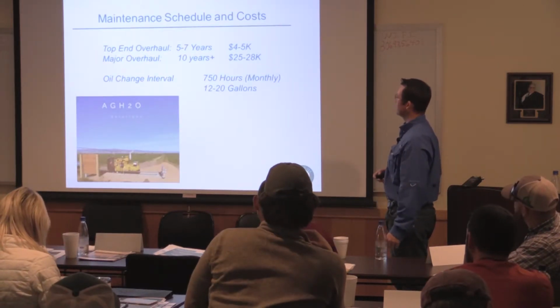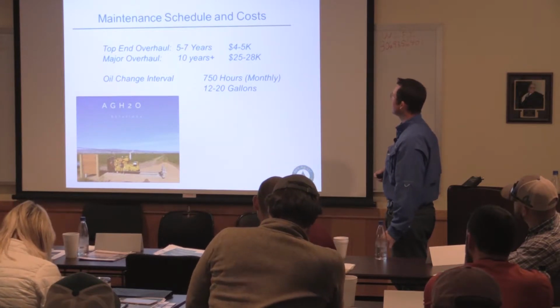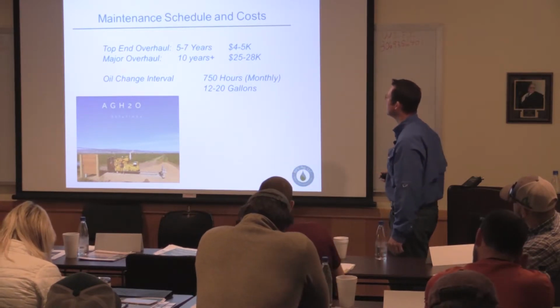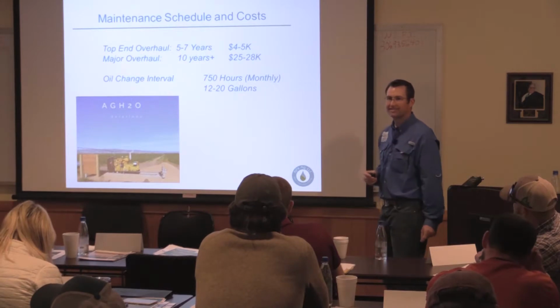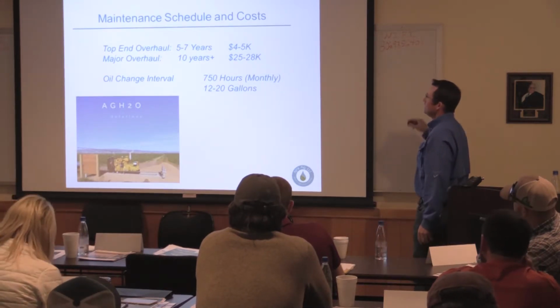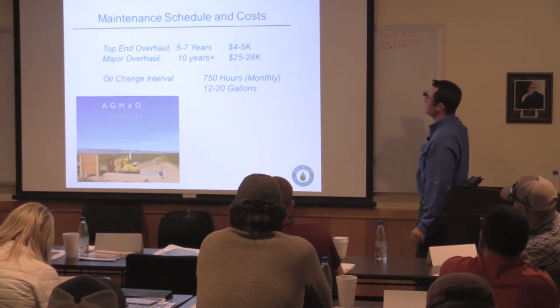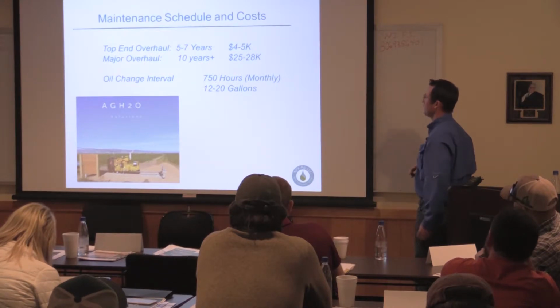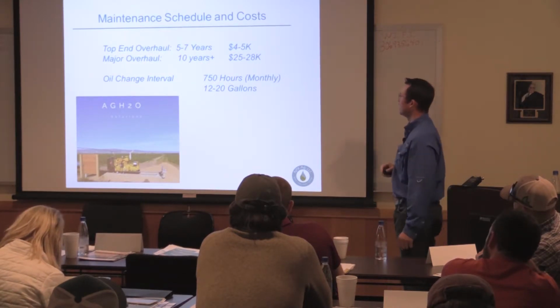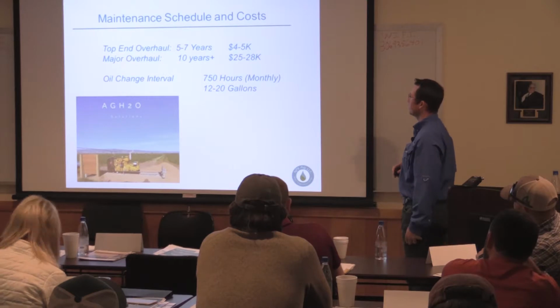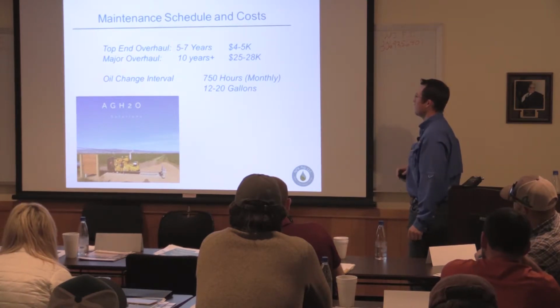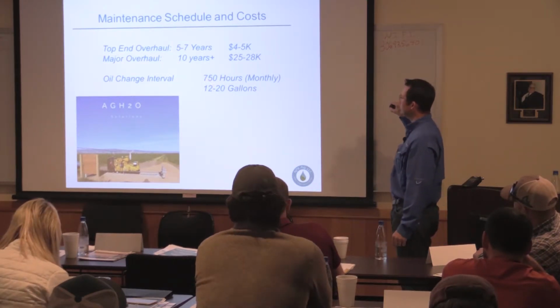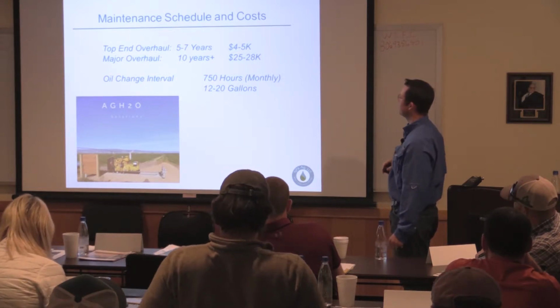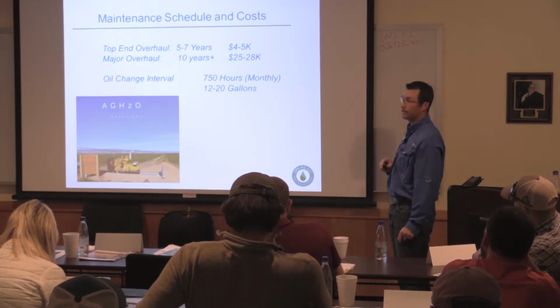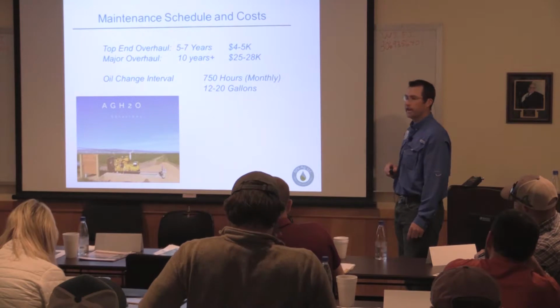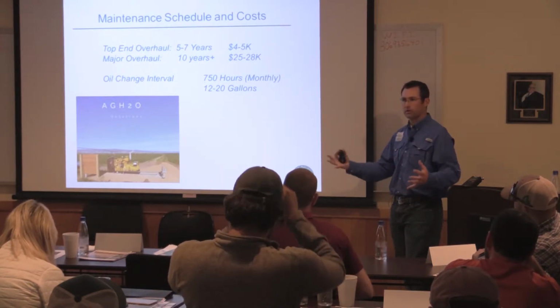Now let's talk about maintenance schedule and costs. Top end overhaul, again for an industrial motor, is looking at 5 to 7 years at a cost of $4,000 to $5,000. Major overhaul is looking at 10 years plus, depending on how you run it, just shy of $30,000. Your oil change interval on these motors is about 750 hours, roughly monthly, and you're looking at 12 to 20 gallons depending on whether you've got a 4-cylinder, 6-cylinder, or whatever.